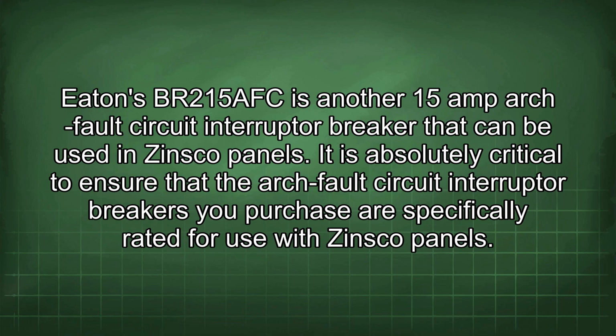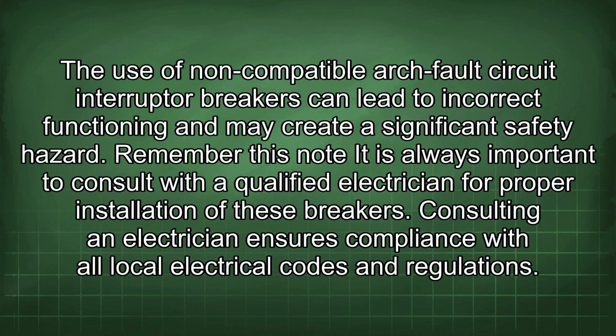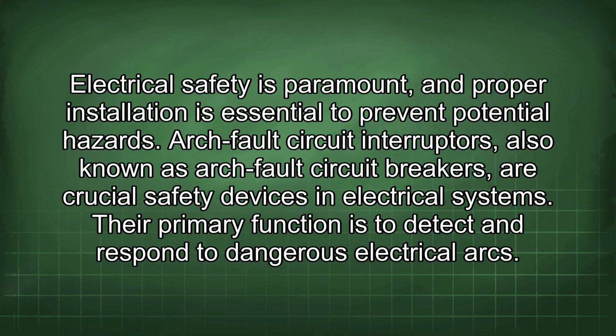It is absolutely critical to ensure that the arc fault circuit interrupter breakers you purchase are specifically rated for use with Zinsco panels. The use of non-compatible arc fault circuit interrupter breakers can lead to incorrect functioning and may create a significant safety hazard. Remember this note: it is always important to consult with a qualified electrician for proper installation of these breakers. Consulting an electrician ensures compliance with all local electrical codes and regulations. Electrical safety is paramount, and proper installation is essential to prevent potential hazards.